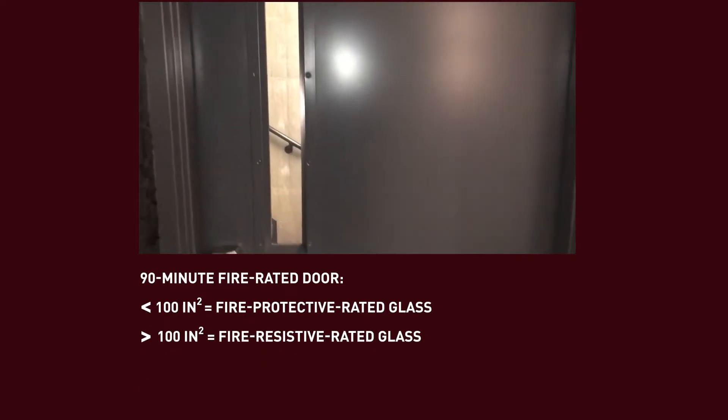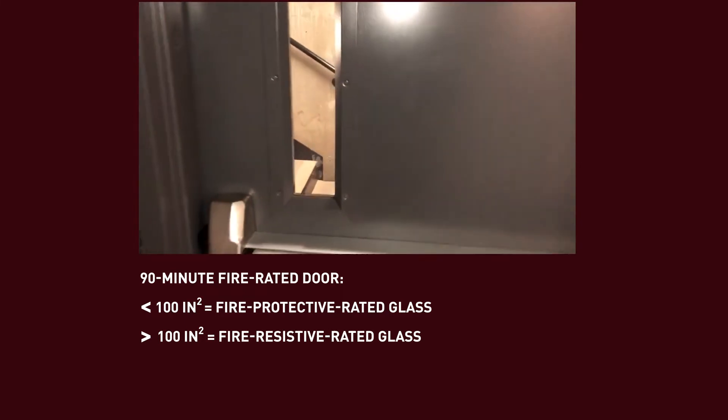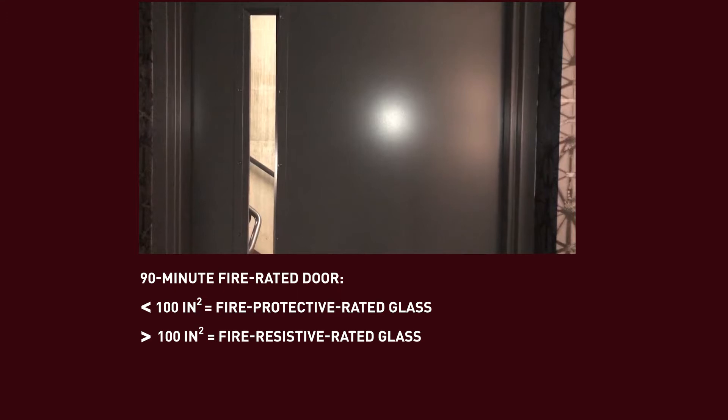In that door you can put 100 square inches of this kind of glass. This happens to be a FireLite NT application, and if you use any more than 100 square inches you have to use a different resistive product called Pyrostop.